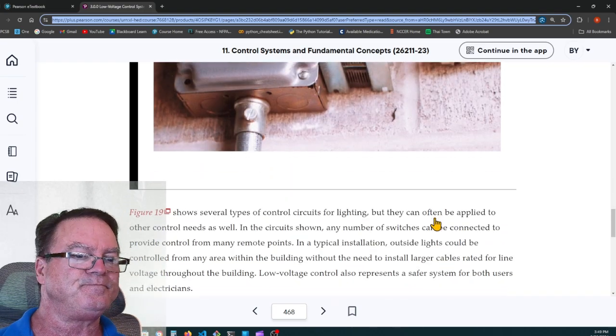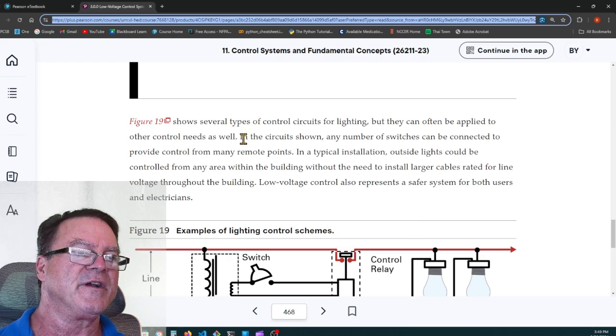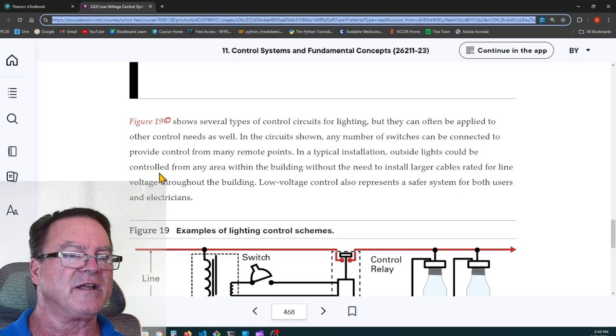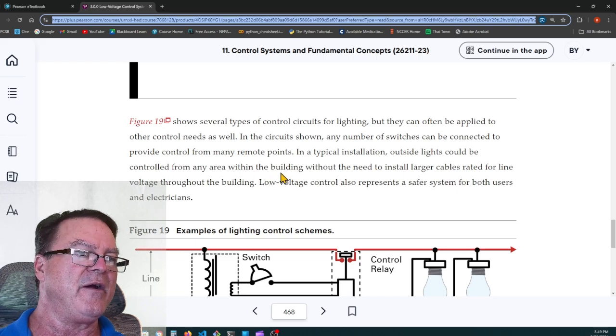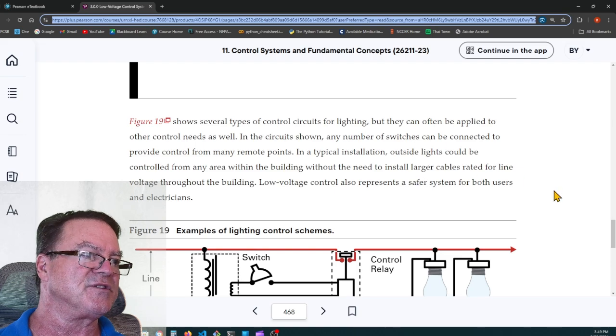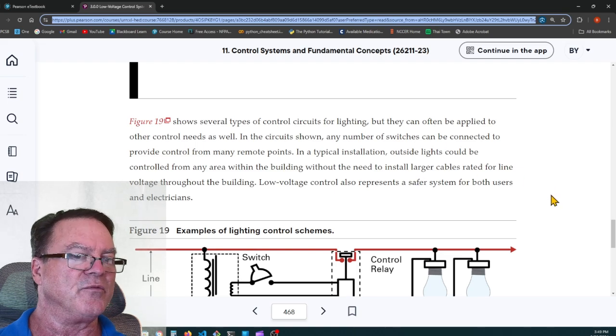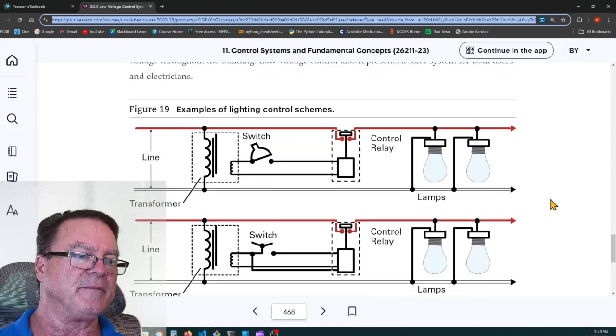So, Figure 19 shows several types of control circuits for lighting. They can often be applied to other control needs as well. The circuit shown, any number of switches can be connected to provide the control for many remote points. In a typical installation, outside lights can be controlled from anywhere area within the building without the need to install larger cables rated for line voltage throughout the building.